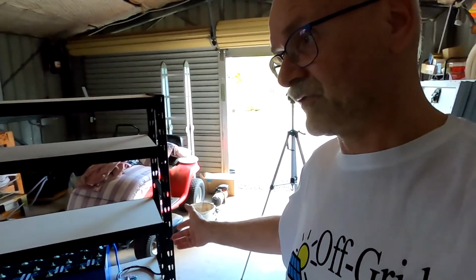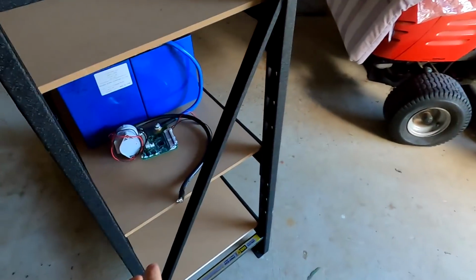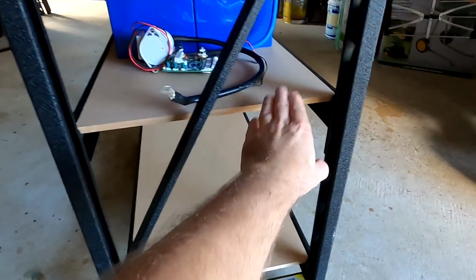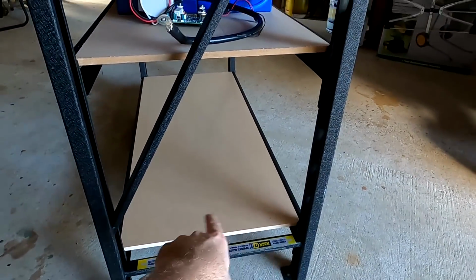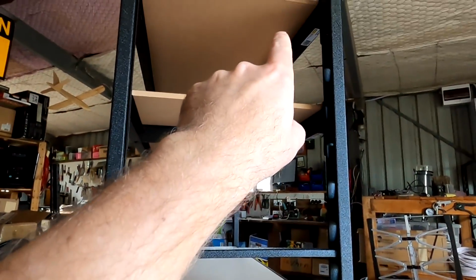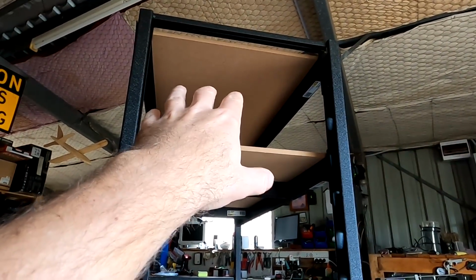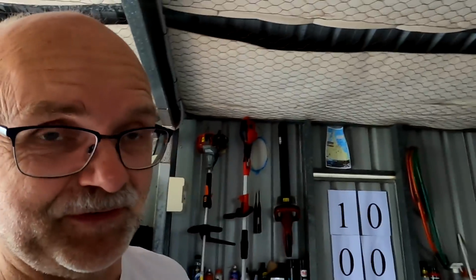Or I can use a bus bar, having a positive and a negative running all the way from the bottom to the top of the shelf, and then connect our switch gear up in the top compartment. They're not cheap - this is like $100 per meter for tinned copper bus bar.